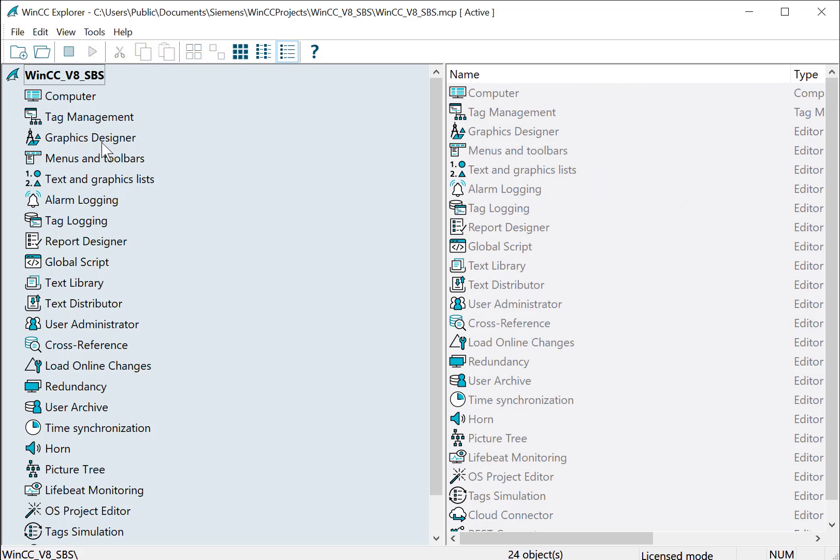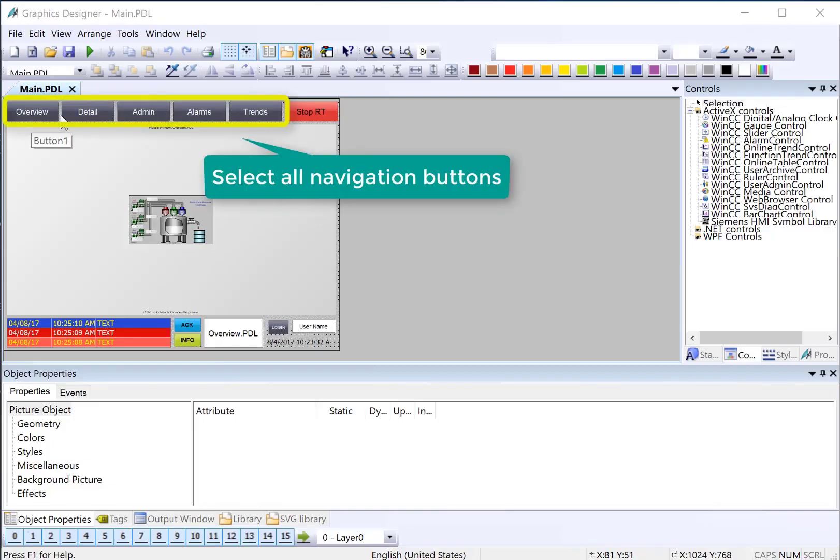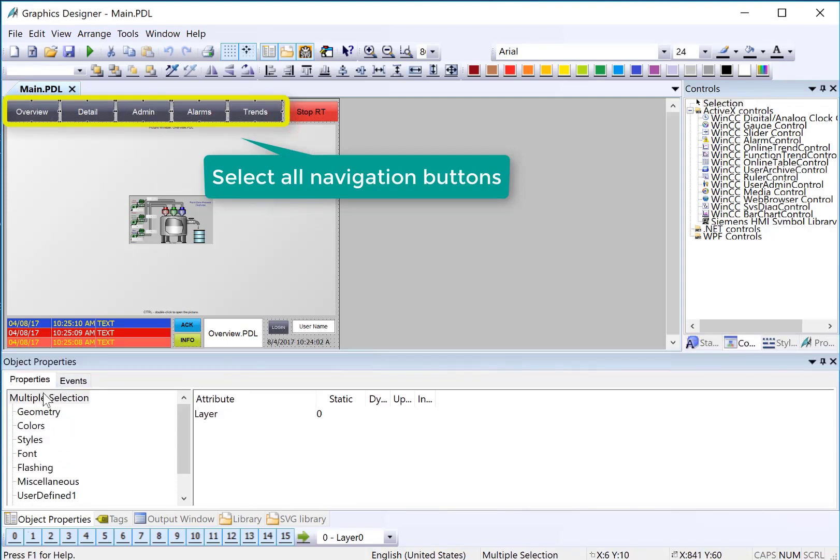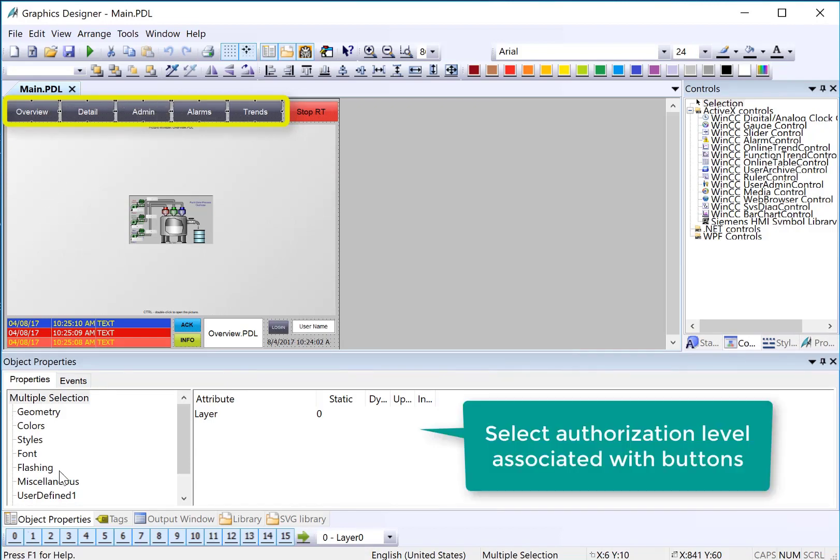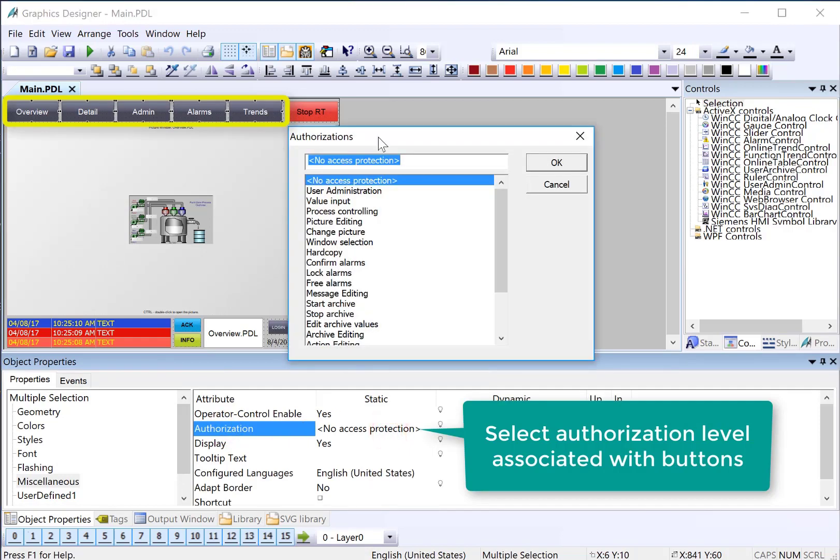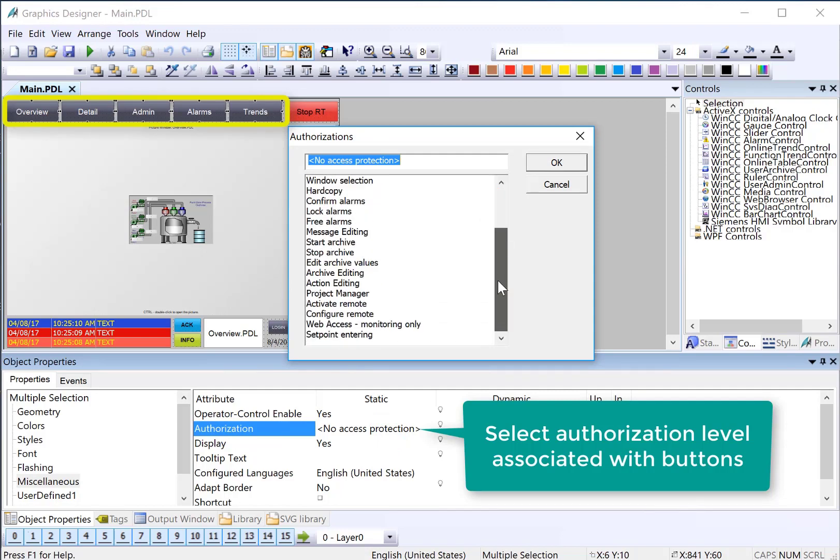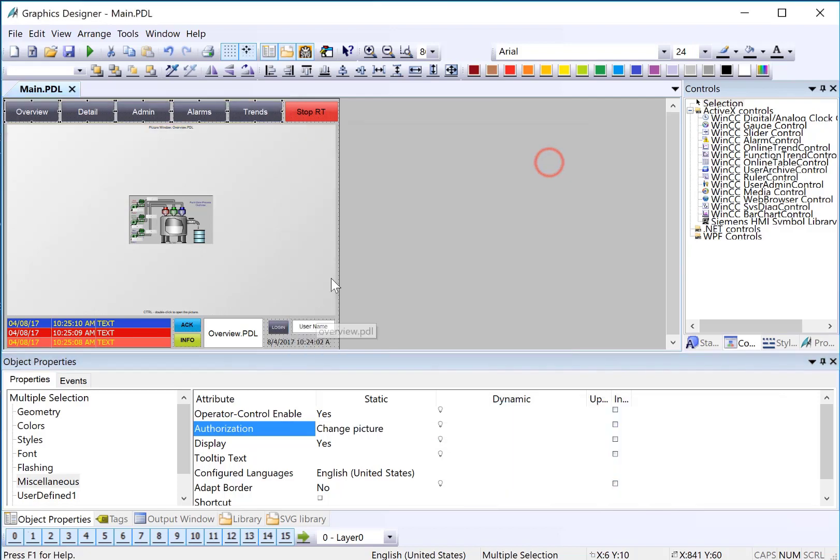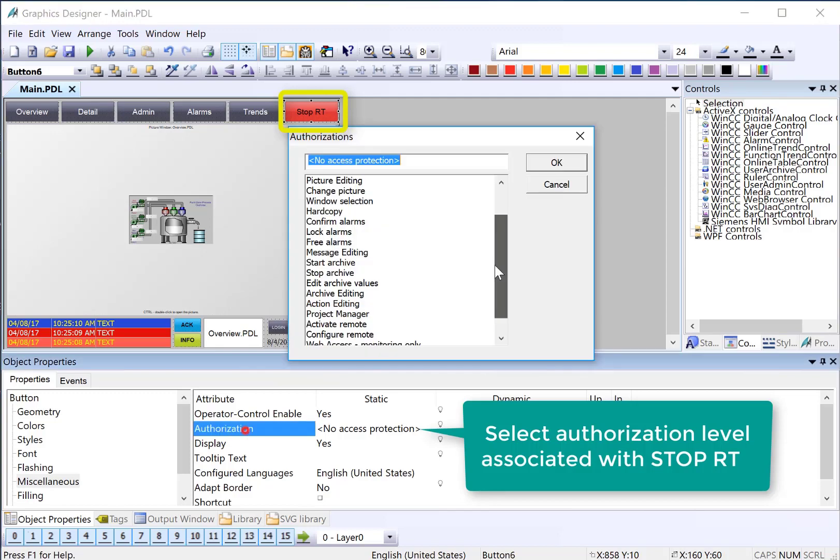Now we need to go into our graphics designer pages and assign authorization levels to the objects. We'll start with our navigation buttons. I'm just going to lasso all of our navigation buttons. In the properties dialog you can see it says multiple selection so that means it's properties of all these buttons. Under miscellaneous we have the authorization attribute and if we double click here it gives us the same list that we saw in user administrator. We're going to assign one of these to be required in order to access these buttons. So we will do change picture and just click OK. So each individually these buttons have the change picture authorization.